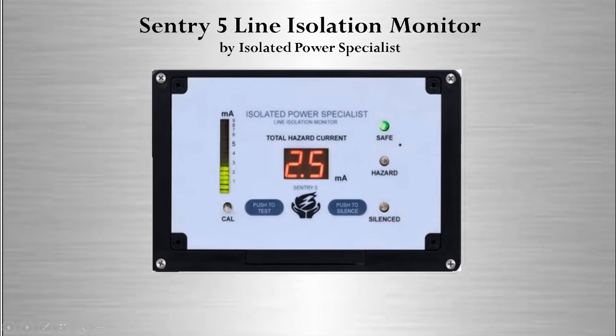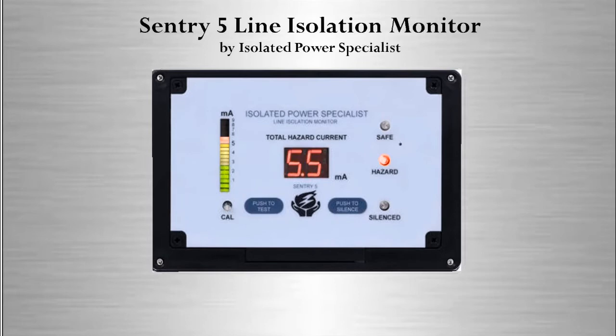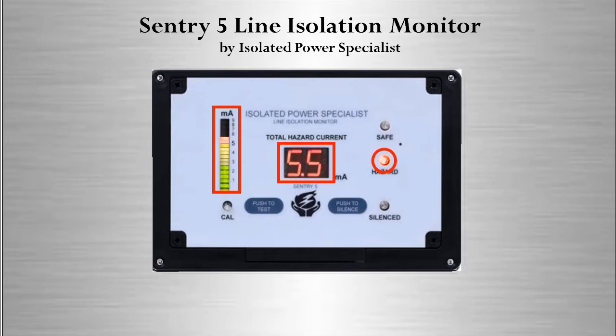This is the state-of-the-art line isolation monitor distributed by Isolated Power Specialists. As the NFPA code stated, there is a green light when in the safe mode, and a red light when in alarm, accompanied by an audible alarm. On the Sentry 5, you will notice a digital readout in the middle of the monitor showing the amperage of 5.5 milliamps. A colorized bar graph shows the increase or decrease in association with the digital readout. Additionally, it has two buttons: the push-to-silence button to turn off the audible alarm — but it will not turn off the red alarm light — and a push-to-test button to initiate a self-test.